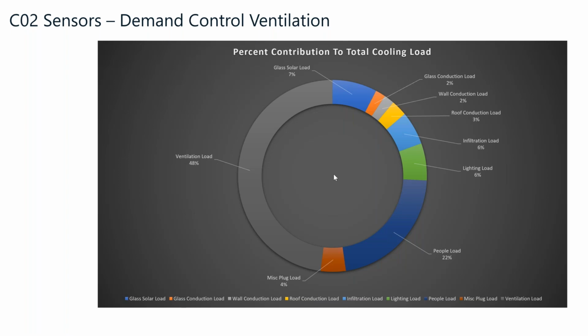What's on the diagram here is when we isolated just the cooling for the building, about 48% of the load within the building goes to ventilation air. So that's why controlling that ventilation air becomes so important to us, where if we can cut our ventilation just in half, we can cut our cooling load down by 25%.